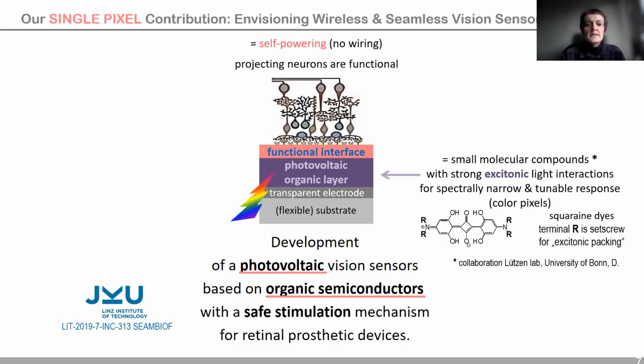Photovoltaic means that the electrical signal is directly generated by the device upon illumination with light. This means light comes in, an electrical bias or say stimulus goes out, and this avoids wiring and an external power supply. The photovoltaic pixel is supposed to restore light sensitivity only. That means it should replace only the degenerated photoreceptors, while all projecting neurons are still functional. Therefore, the device should provide a safe stimulation to the remaining healthy tissue, requiring only a low-intensity light trigger.